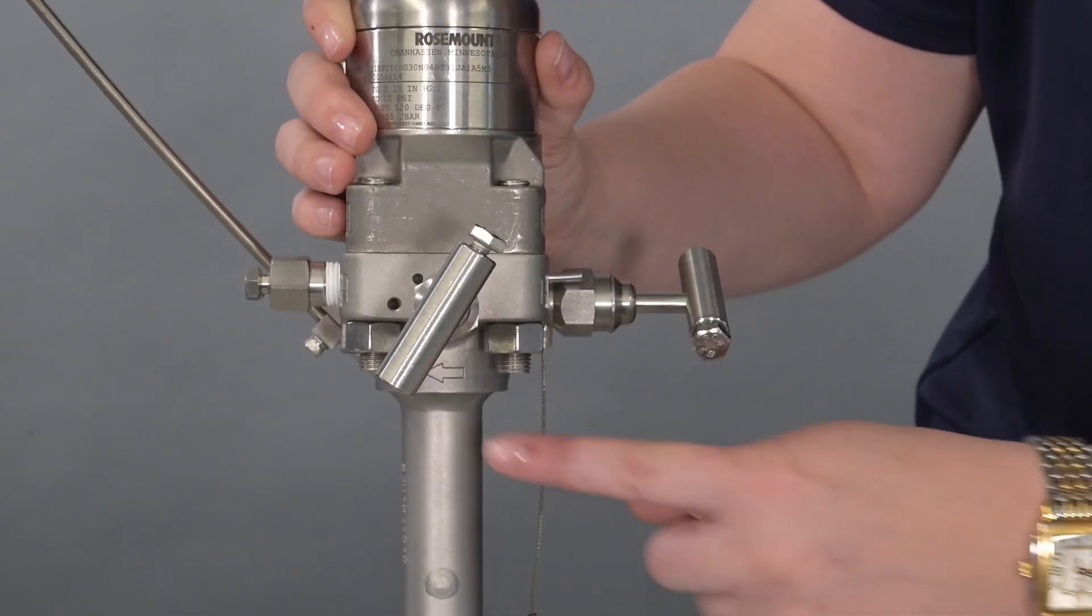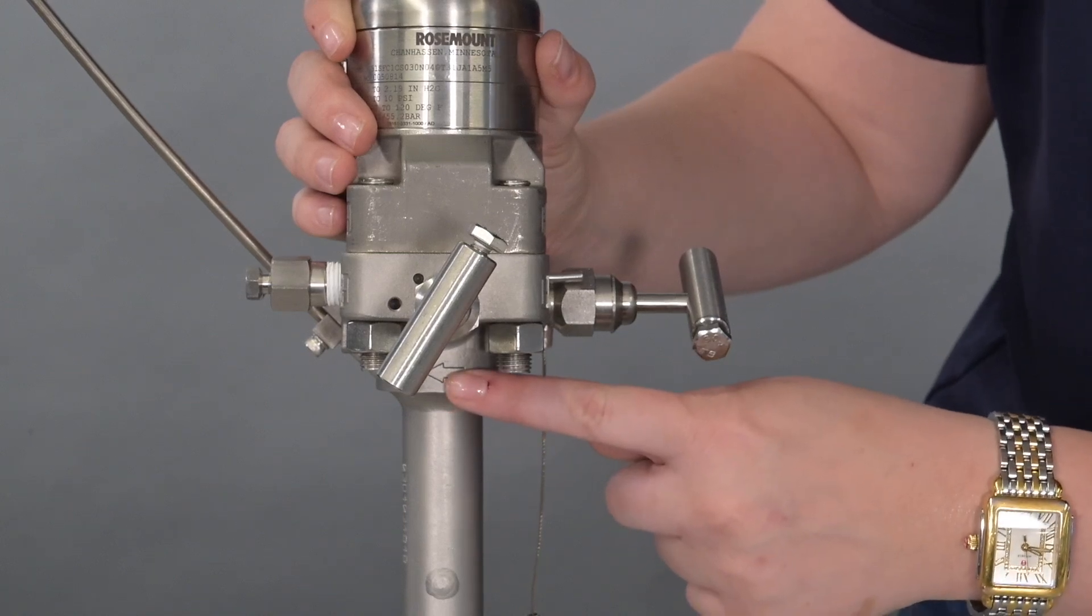We should also verify the flow direction on the arrow of the neck of the 405. Now we can check to make sure we have the proper straight run requirements for the line size. In most cases, a conditioning orifice plate will only need a straight run of two pipe diameters upstream and two pipe diameters downstream.